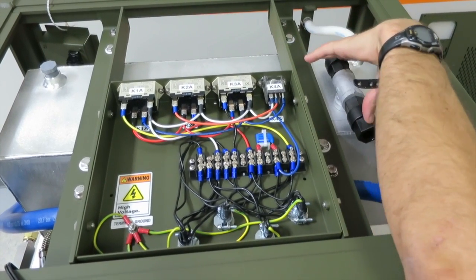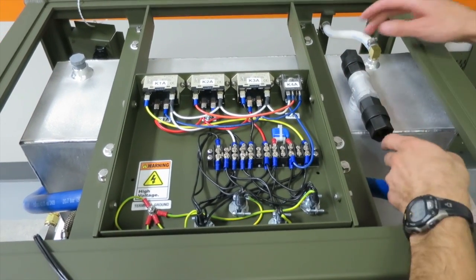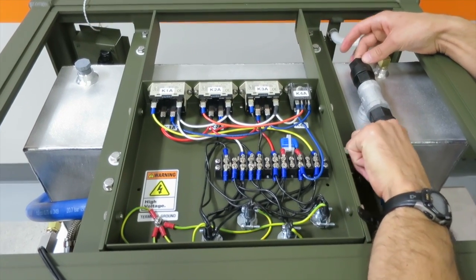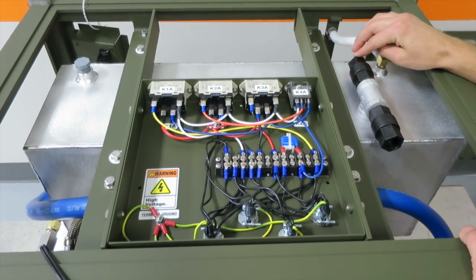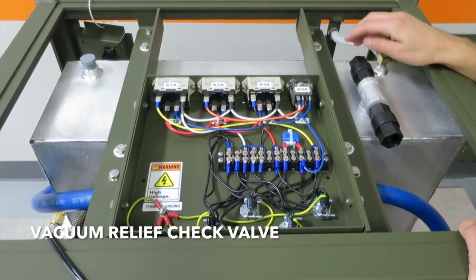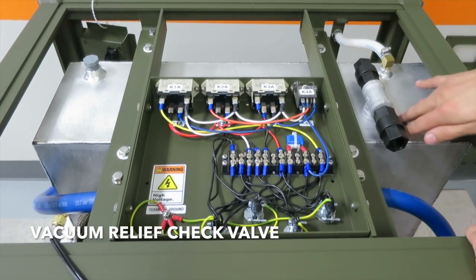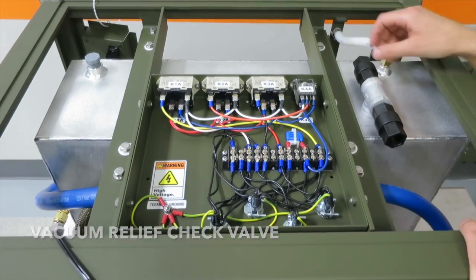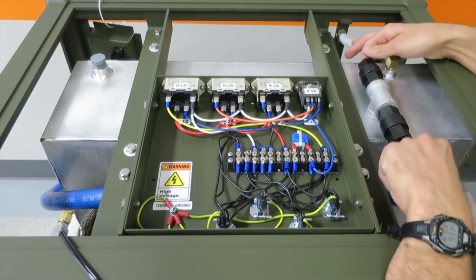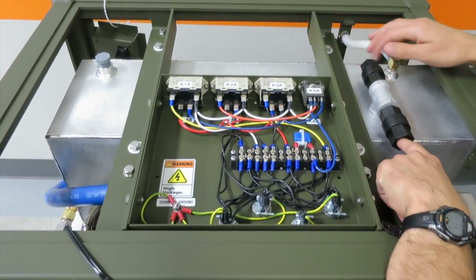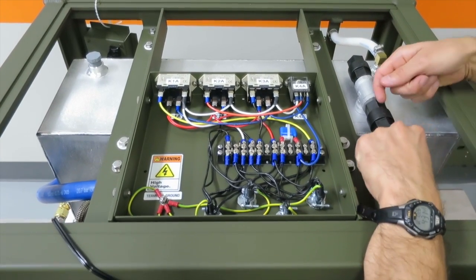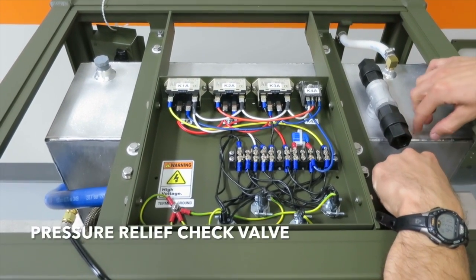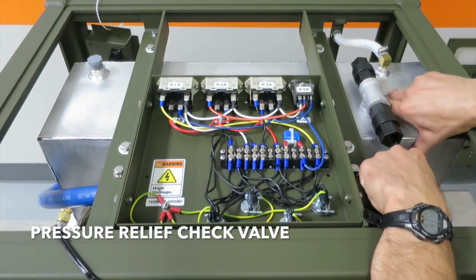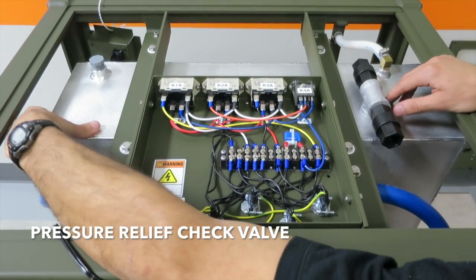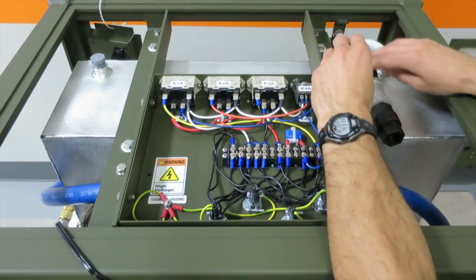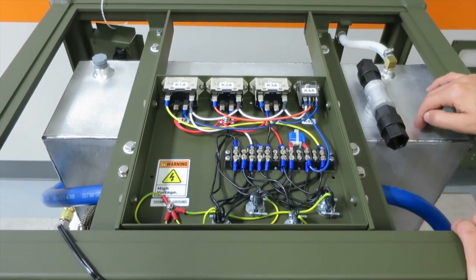Right here we have the two check valves I previously mentioned. This one is protecting from vacuum. Again, we don't want any vacuum or pressure to form in this tank. Low pressure is okay, but this allows air to be sucked in and relieve any vacuum that might form. This allows any pressure to escape, so pressure doesn't form in this tank. Because again, this tank was designed just to hold the water and not to hold pressure. And that's it for the top.